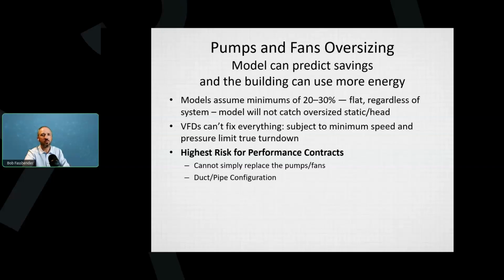Now, the reason this is really high risk for performance contracts is you can't simply replace the pumps and fans. The duct and pipe configuration is also designed on top of it. And so in this particular case, the pipes needed to be torn out and reinstalled, and it was really expensive.